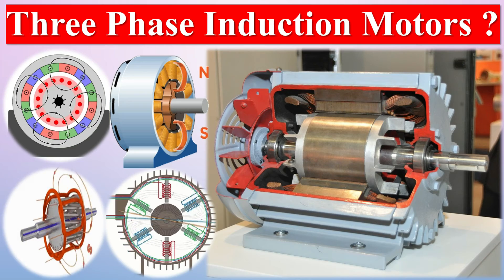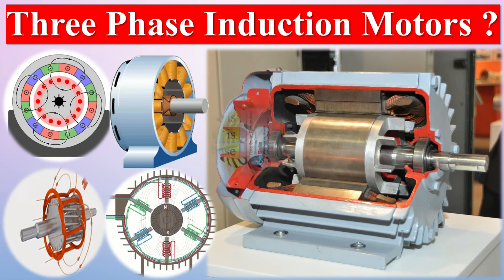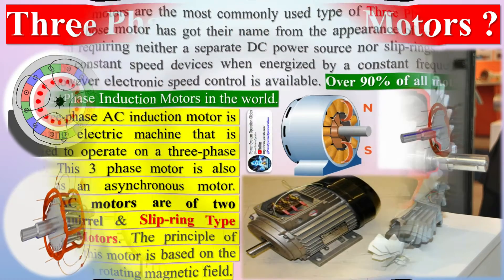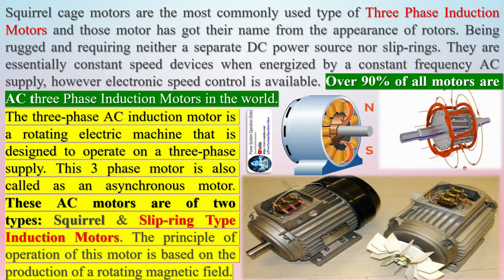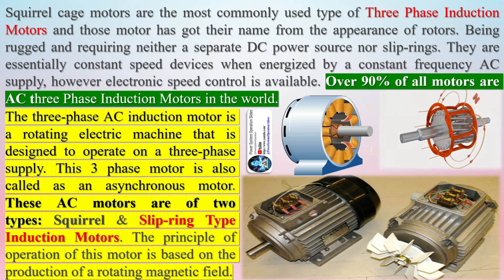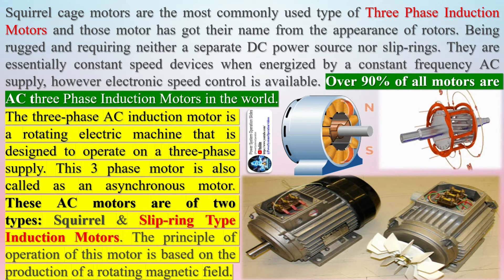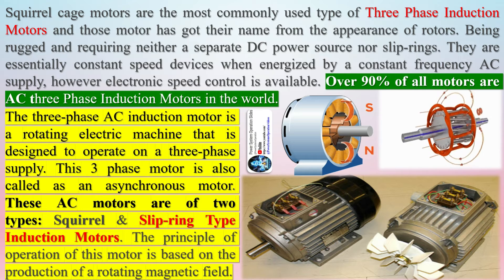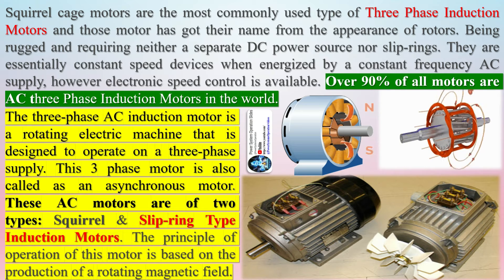Squirrel cage motors are the most commonly used type of three-phase induction motors, and these motors got their name from the appearance of their rotors. Being rugged and requiring neither a separate DC power source nor slip rings, they are essentially constant speed devices when energized by a constant frequency AC supply; however, electronic speed control is available.